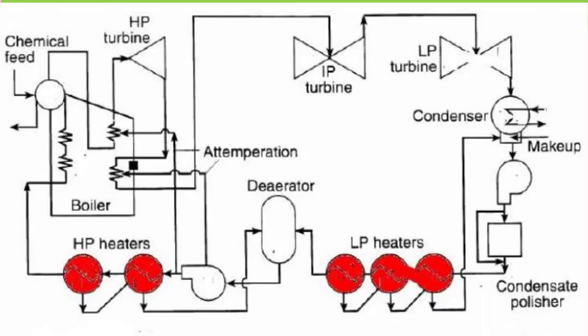A deaerator is a special case of the open feed water heaters, which is specifically designed to remove non-condensable gases from the feed water. Closed type feed water heaters are typically shell and tube heat exchangers where the feed water flows through the tube and the extracted steam condenses outside the tube in the shell. The closed heaters are costly and may not give as high a feed water temperature as open heaters. A closed heater requires only a single pump for the main feed water stream regardless of the number of heaters.